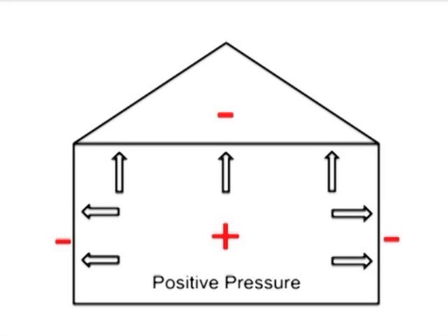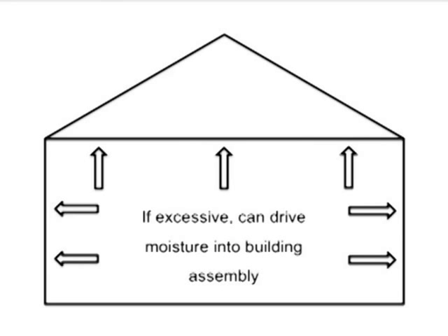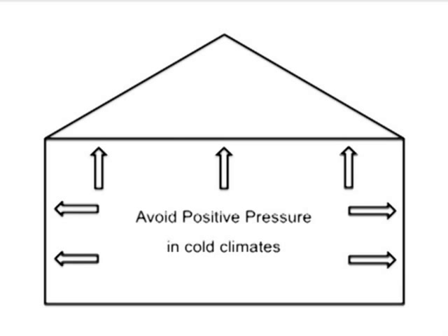Positive pressure in buildings means there is pressure exerted outward on building components. Excessive positive pressure can drive moisture-laden air into building walls, ceilings, and floors, and present durability problems. Positive pressures should be avoided in cold climates.